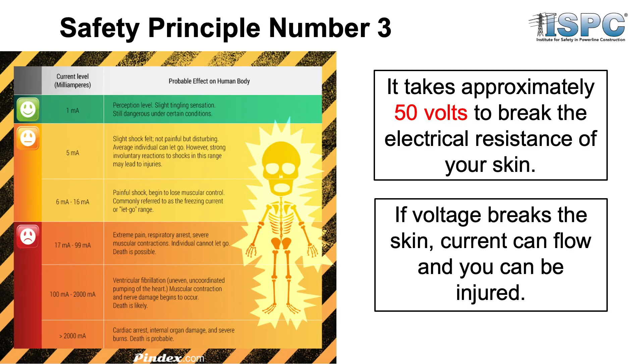So, grounding. At least in my experience, this is a very, very misleading phrase. Very misleading, right? Grounding for the protection of personnel. We're not grounding for the protection of personnel, okay? Grounding does not assure that a worker is not going to get shocked or electrocuted, okay? The number one purpose for grounding is to trip, okay? Should something happen, should something become accidentally energized, a fault on the system, a switching error maybe, our grounding is meant to isolate that fault as quickly as possible, right? To minimize what you as the worker in that work zone see to your personal self. But it doesn't mean you're not going to see anything.